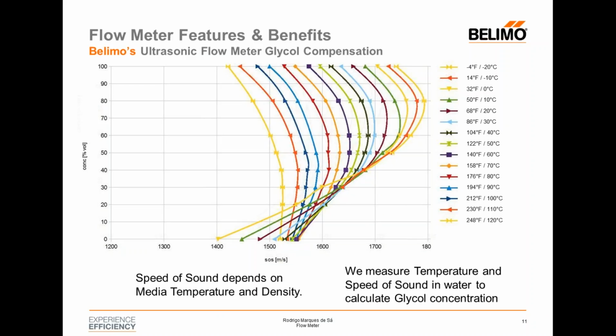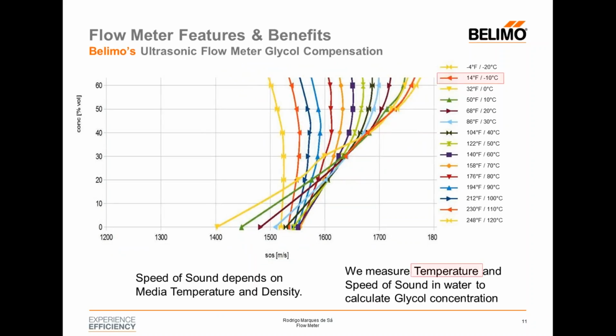So we measure the temperature here, just as an example to show you, and we also measure the speed of sound. In that way we are able to calculate the concentration of the glycol, for example, here showing 50% glycol. That's why we have this differential feature in our ultrasonic flow meters.